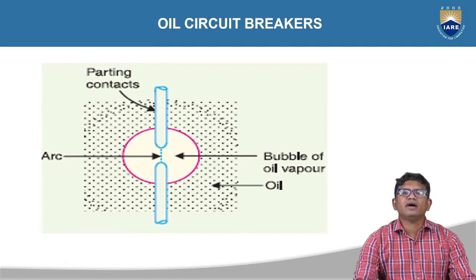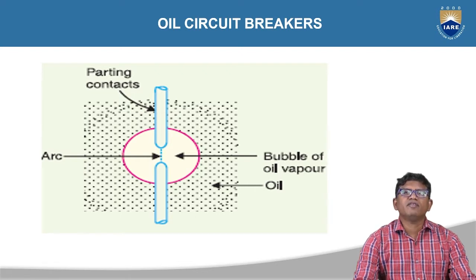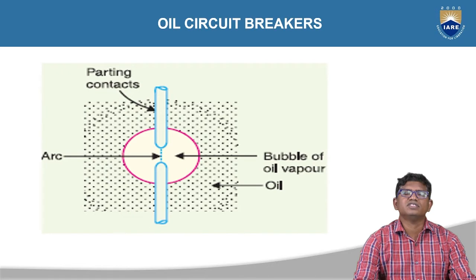Under abnormal conditions, excess current flows through the contacts of the breaker. The contacts get overheated. By utilizing this heat energy, the oil is vaporized. The vaporized oil is disassociated into various gases, and the major gas is hydrogen gas.